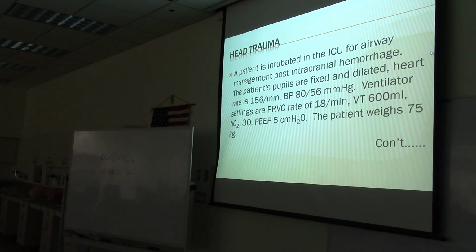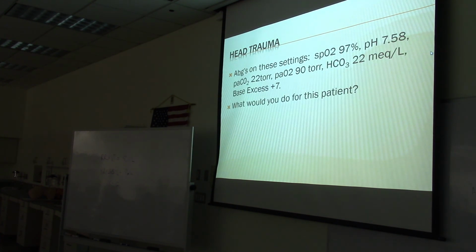Okay. So the new minute volume, it says 9.8. Minute volume divided by 600. Minute volume divided by tidal volume gives you respiratory rate. 10? Okay. 9.8. All right, so we fixed this patient too. We're busy today.